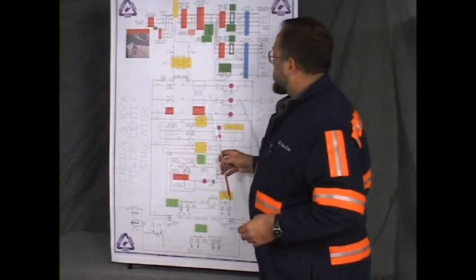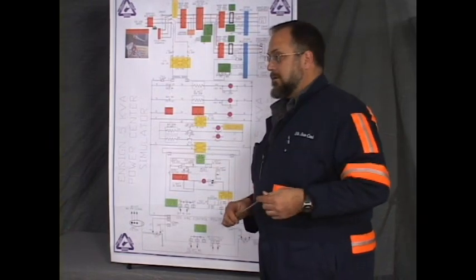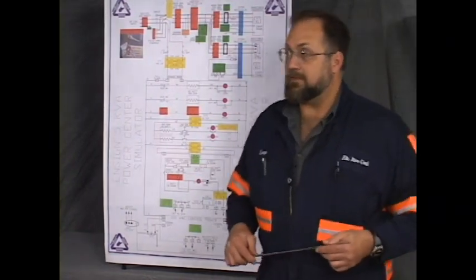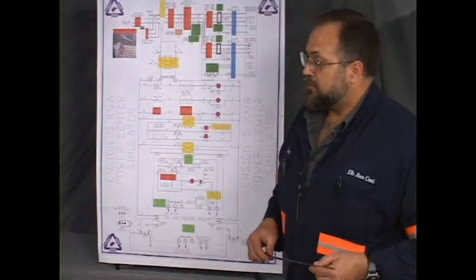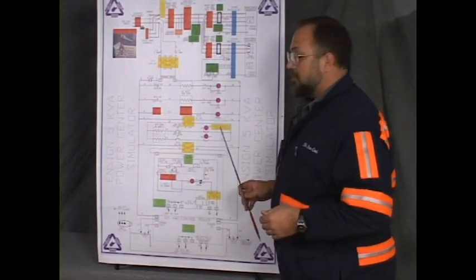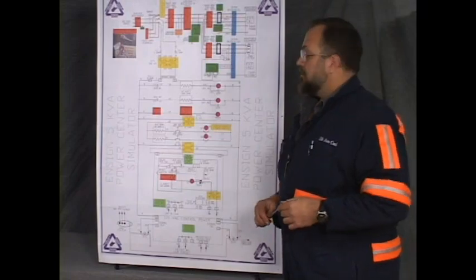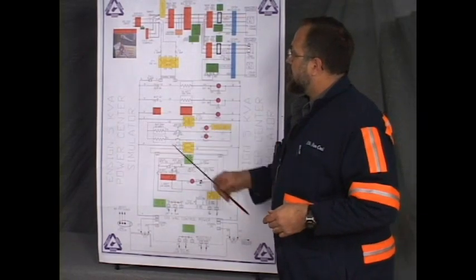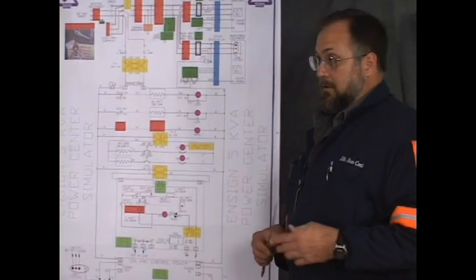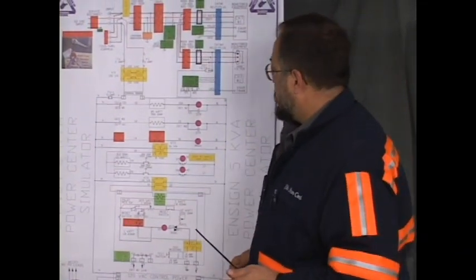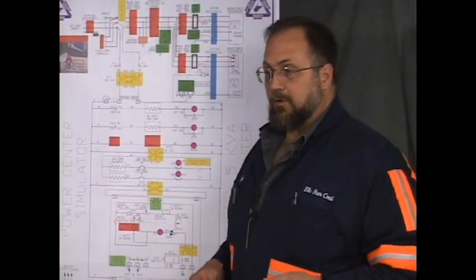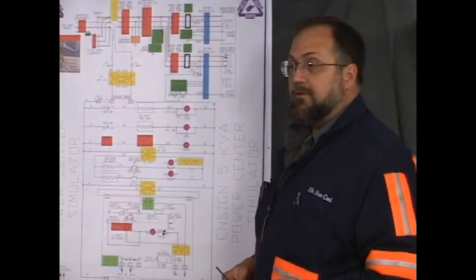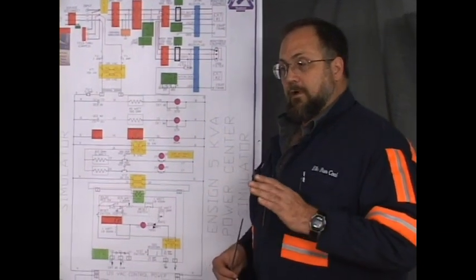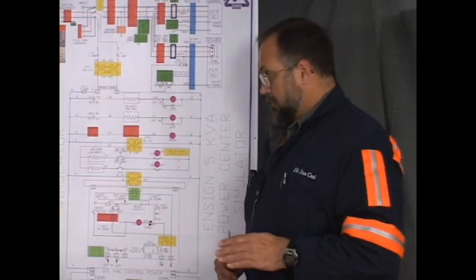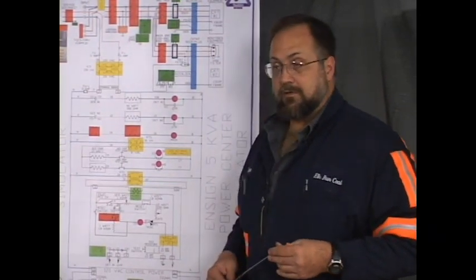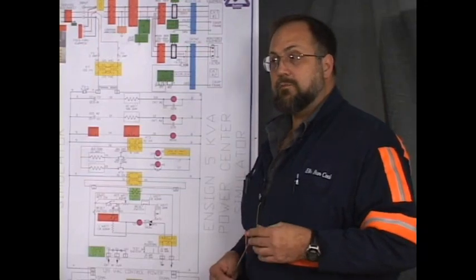It says that GCS1 will not pick up. As we mentioned earlier, GCS1 is the contacts that control the circuit breaker from the ground continuity monitor. Now, the ground continuity monitor contacts won't pick up. A certain situation has to be met before the ground continuity monitor contacts will pick up. You have to have a continuous path on the ground conductor in the receptacle to the machine and then back. It has to have a loop.